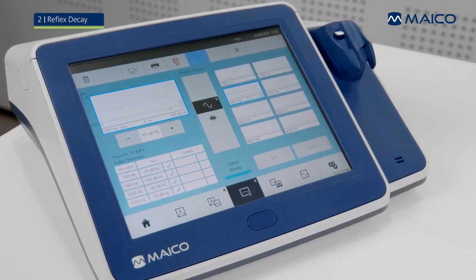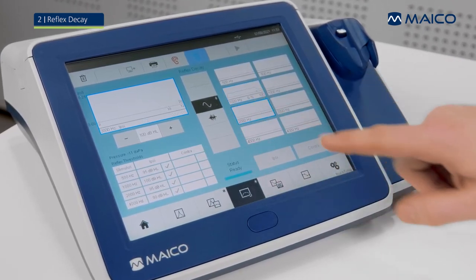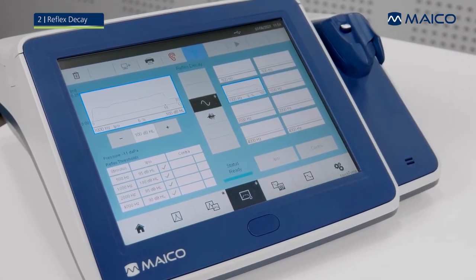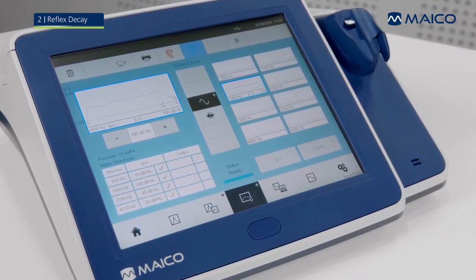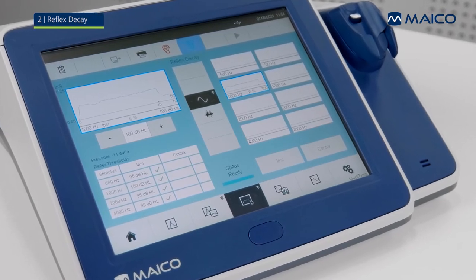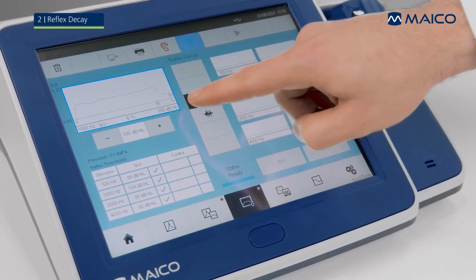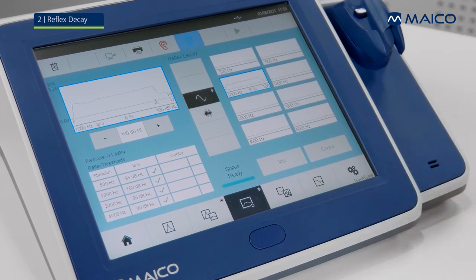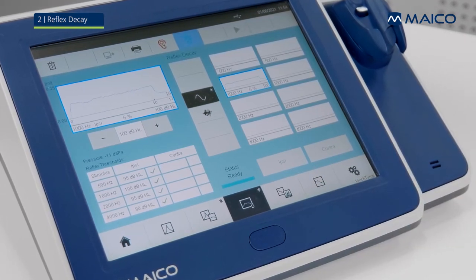When testing is complete, previous measurements can be reviewed in the large window by selecting the small stimulus box on the right side of the screen. In the large window, the compliance progression over time is displayed. The block below shows the frequency, the decay result, and the intensity.